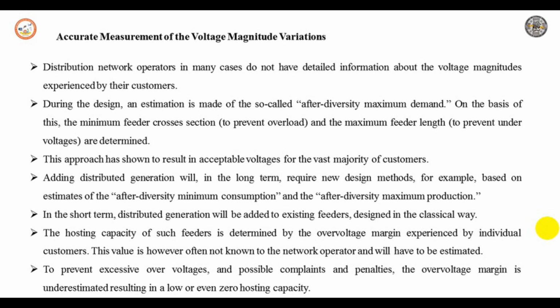The hosting capacity of such feeders is determined by the overvoltage margin experienced by individual customers. This value is, however, often not known to the network operator and will have to be estimated. To prevent excessive overvoltage and possible complaints and penalties, the overvoltage margin is underestimated, resulting in low or sometimes even zero hosting capacity. An accurate measurement of the overvoltage margin for individual customers will make it possible to determine the hosting capacity more accurately. This strongly reduces the risk of unexpected overvoltage. It will also in most cases allow more distributed generation to be connected to the feeder.